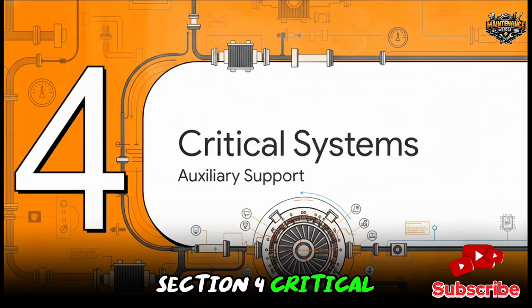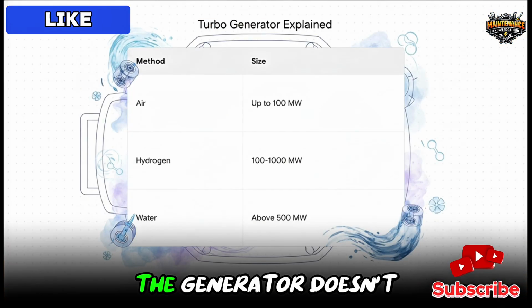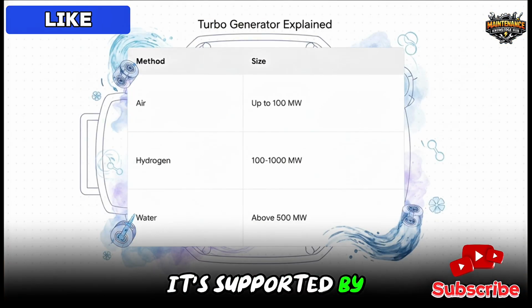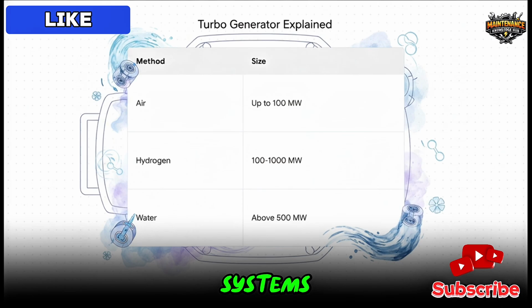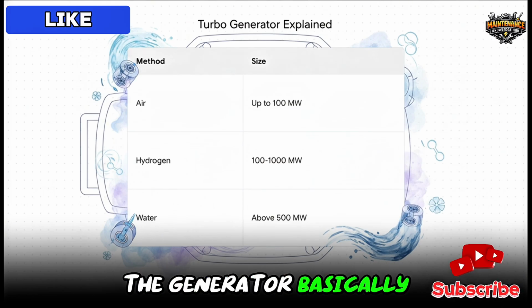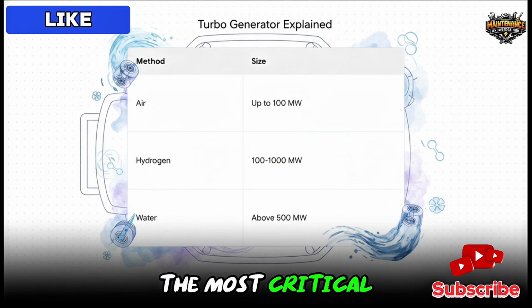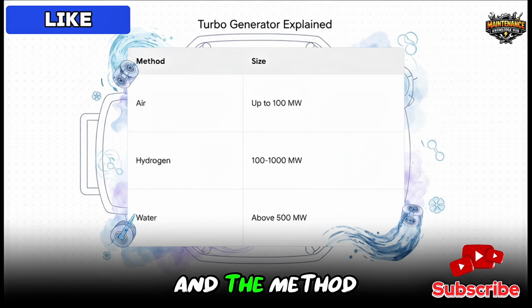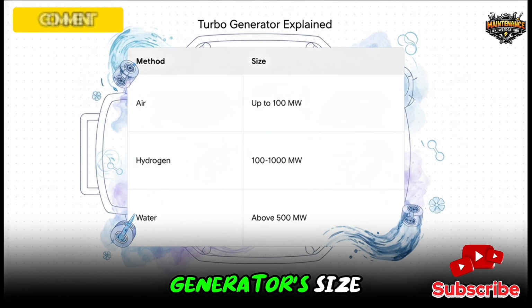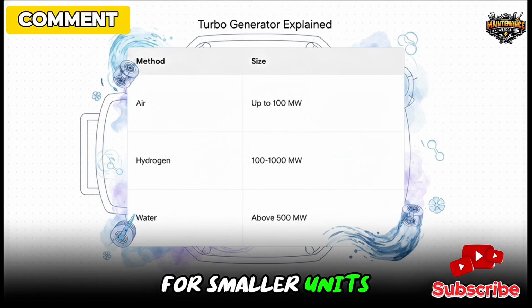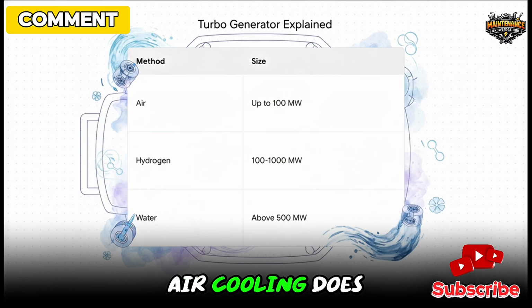Section 4. Critical System Inspections. The generator doesn't work alone. It's supported by highly engineered auxiliary systems. If they fail, the generator basically destroys itself. The most critical of these is the cooling system, and the method you use depends entirely on the generator's size. For smaller units, say up to 100 megawatts, air cooling does the job.